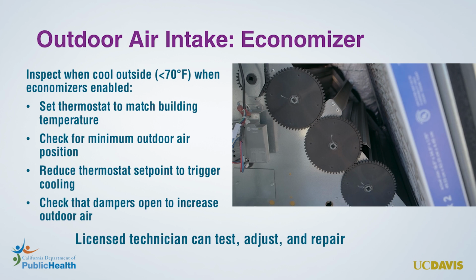Finally, change the temperature on the thermostat to trigger the cooling. The economizer damper assembly should move and increase the outdoor air and decrease the return air. If the damper does not move, then the economizer is not working. Another error that could occur is that the damper assembly might close instead of open the outdoor air damper.